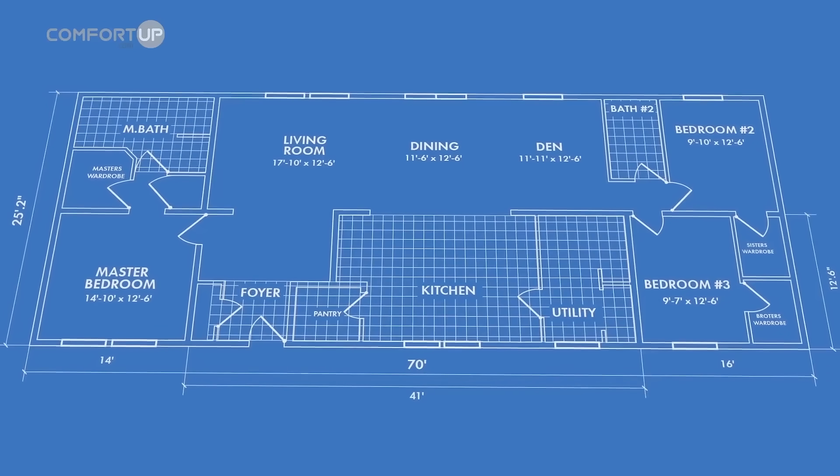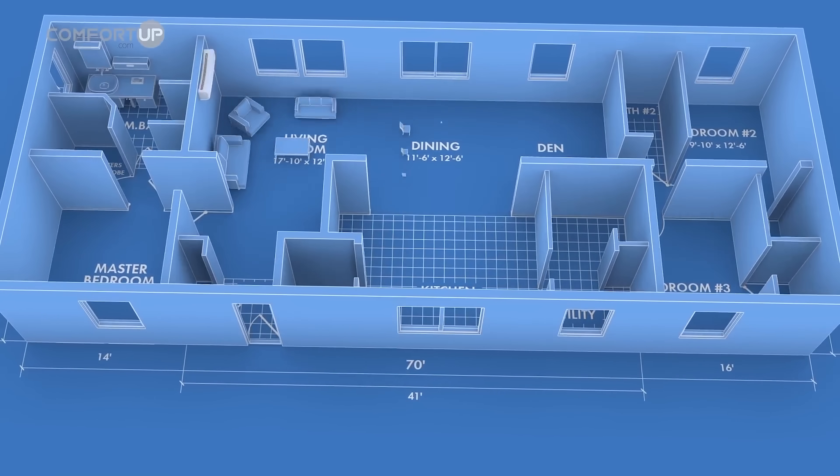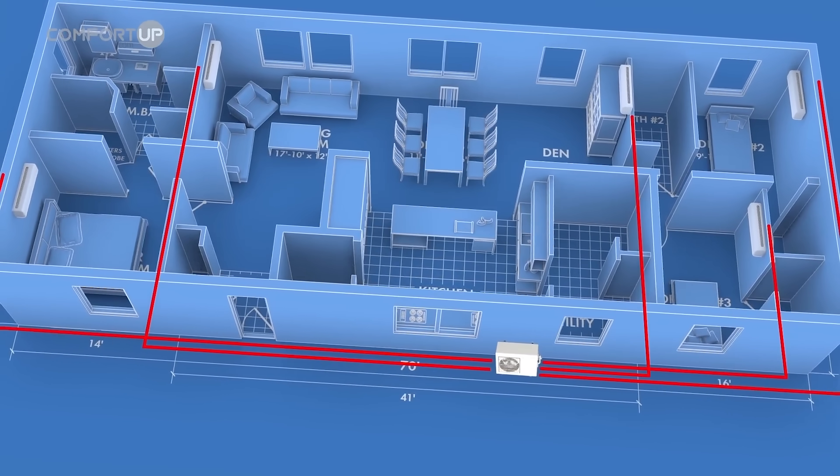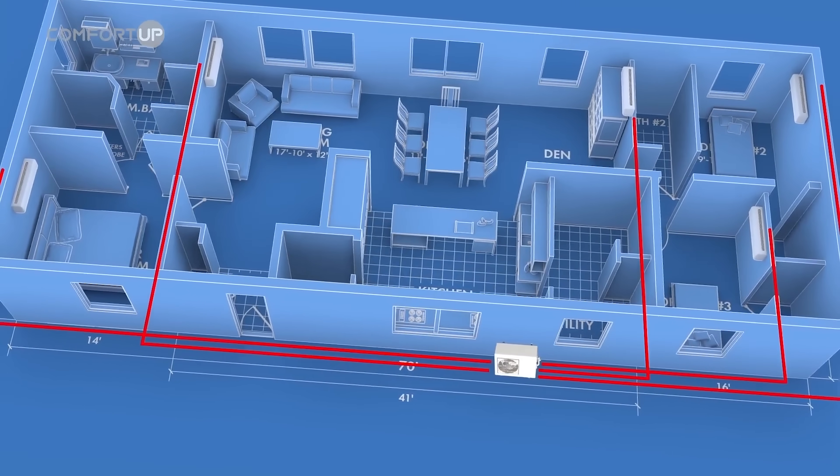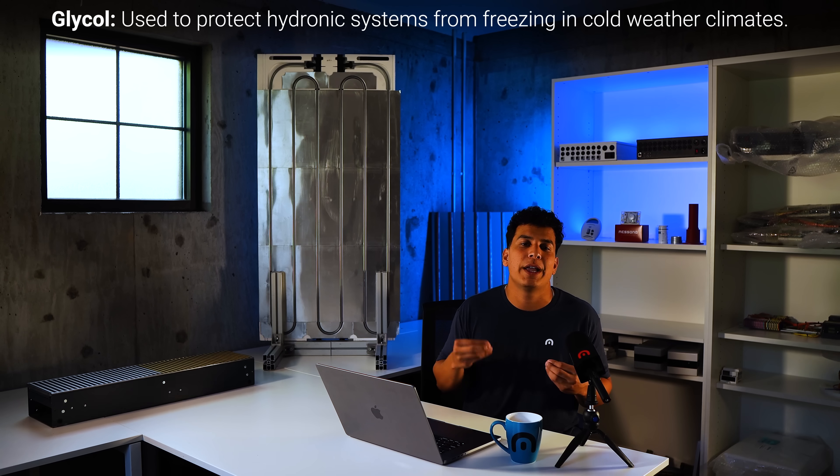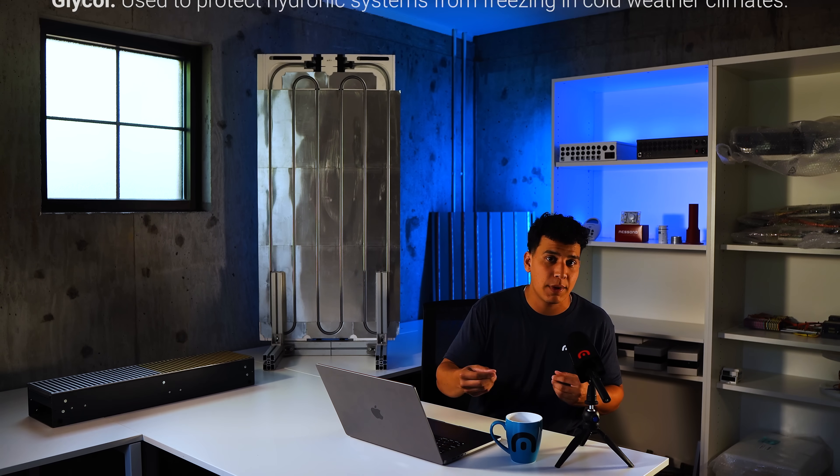And then lastly, the global warming potential of hydronic systems is less. A pretty common system you're seeing nowadays are mini split systems where you have an outdoor unit and then refrigerant lines running to an indoor unit. So that refrigerant is what delivers the heating or cooling. It's what's transporting the hot or cold refrigerant, but refrigerant is toxic. It's not something you necessarily want inside your home. So a hydronic system has a small amount of refrigerant in the outdoor unit, which is used to help heat or cool water. But in terms of what's running inside the home, it's just the hydronic piping. It's just the water lines. Sometimes it's a water glycol mix in really cold climates, but you're not introducing that refrigerant into your environment. And then also GWP refers to the global warming potential. And so all refrigerant is going to end up released to the atmosphere at some point in time. And so because we're using so much less, it is better for the environment using like an air to water heat pump than one of those mini split systems, which have much more refrigerant that is going to eventually be released to the environment.